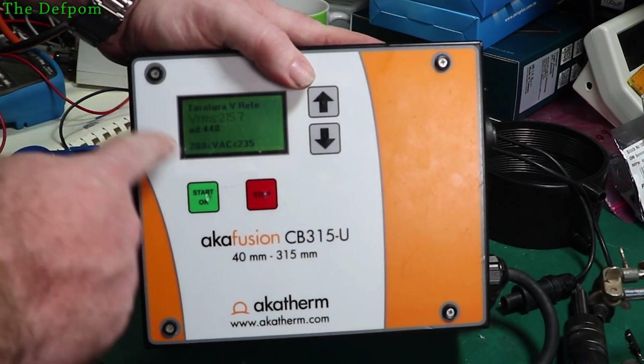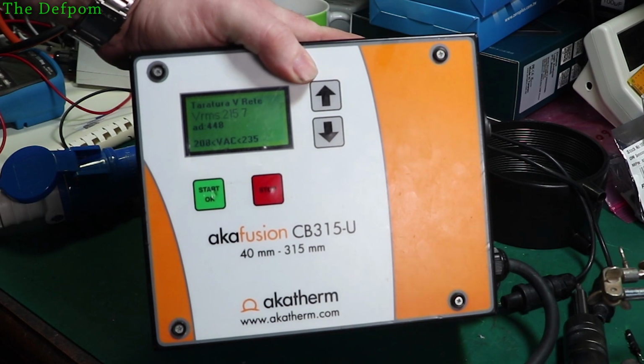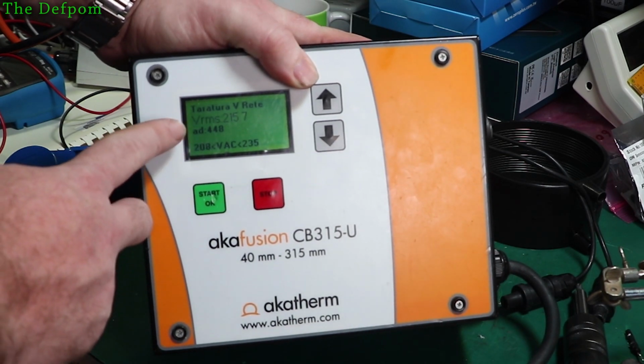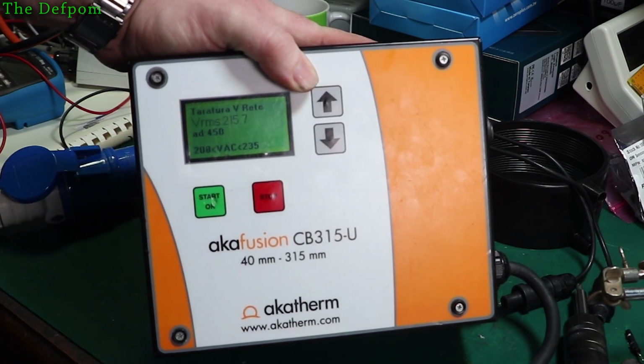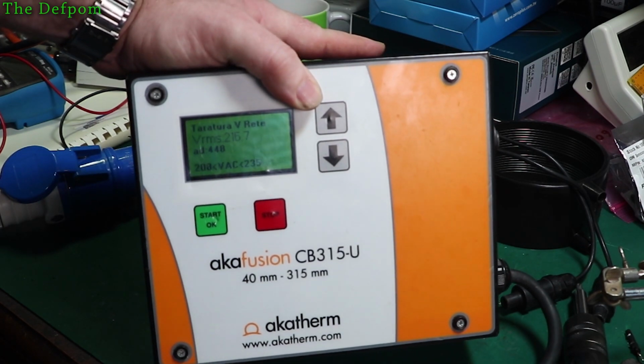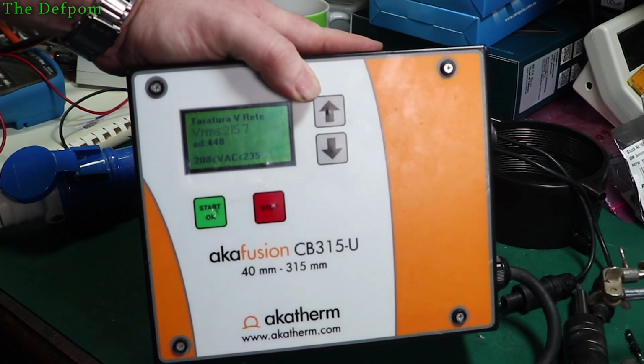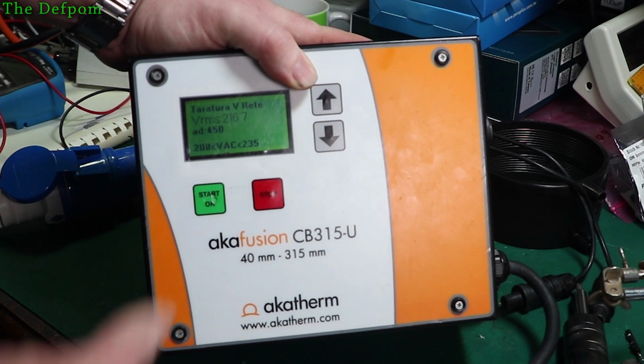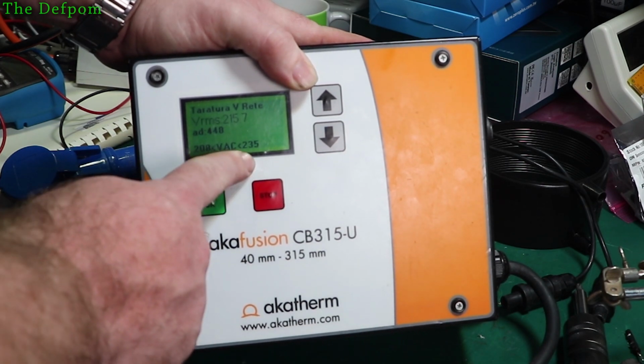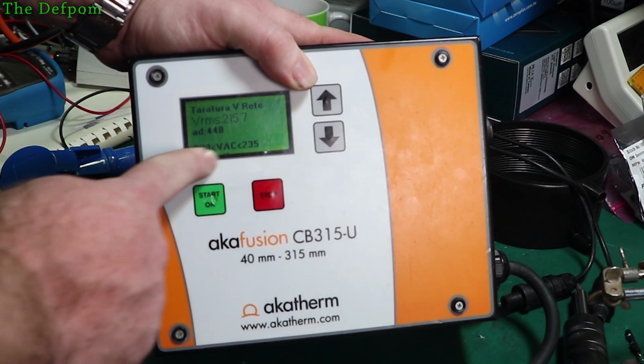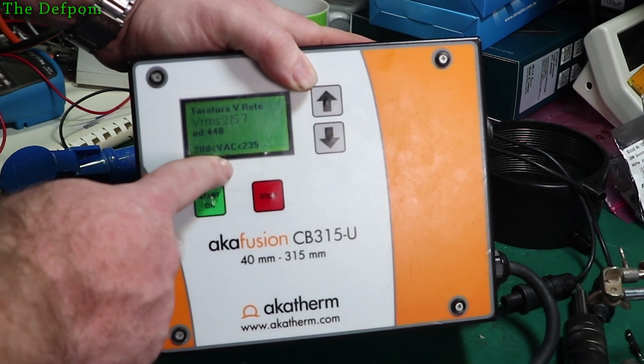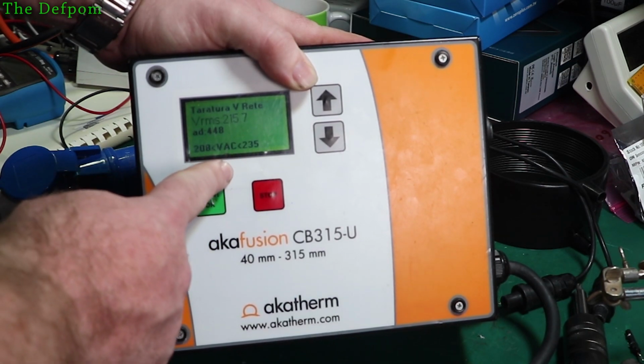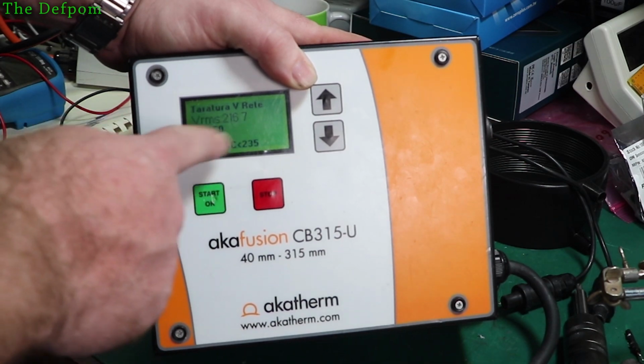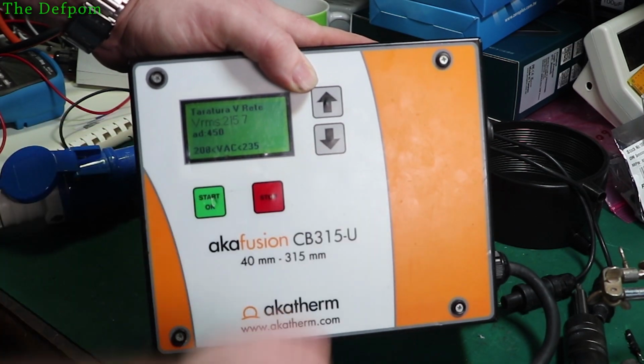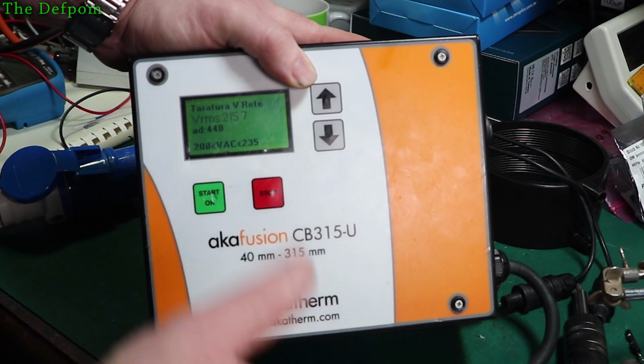This is the voltage measurement on here. Alright, so you can see it's showing volts RMS 215. Well, the actual volts right now is 228 to 230. So it's actually reading a bit low. Now you notice here the range is 208 to 235. So it looks like this is based around a 220 volt system, and so it's been calibrated downwards to make it think it's within that range. There's adjustment inside it, which I think is what does that. I haven't tried that yet.